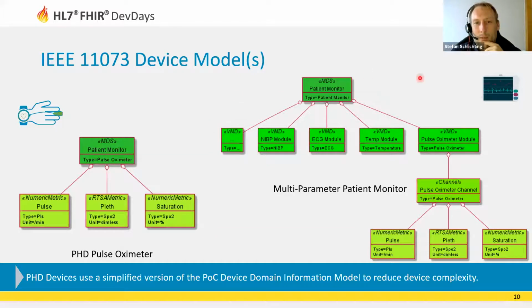If we now look at the other device, which would also monitor the patient, like a multi-parameter patient monitor, you see that there is on top again the medical device system, representing it in this case as a multi-parameter patient monitor, not a pulse oximeter. And there might be other measurement modules here on the level of the so-called virtual medical devices, VMD. For example, we could have a non-invasive blood pressure, ECG or temperature module, and of course also a pulse oximeter module. Below that, inside of the point of care device world, we would have something called a channel, and we could have multiple channels in parallel, for example in the ECG world. Below the channel, we would have the metrics, and these are more or less the same as you can see them here.